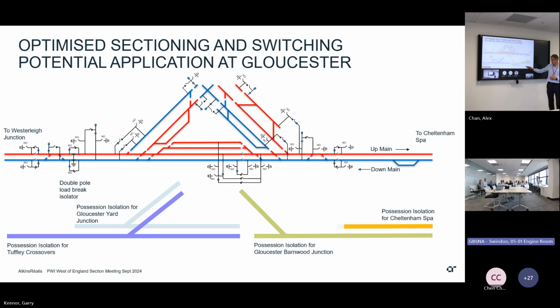We then looked at possession isolations - we know we can isolate under a fault condition, but for a possession isolation, if you wanted to take a possession of the station, your limit of isolation would go all the way back to these sectioning points, because you can't operate trains in this section. With the station out of use and no crossovers, there's nowhere a passenger train can go. For freight trains you have to consider where they might be - if electric freight, they'd go into a siding or freight depot, so you need to look at that too, though most electrics are passenger services at the moment. So just for this station you'd take an isolation at this point, and if you wanted this junction out, that bar shows the limits of possession.